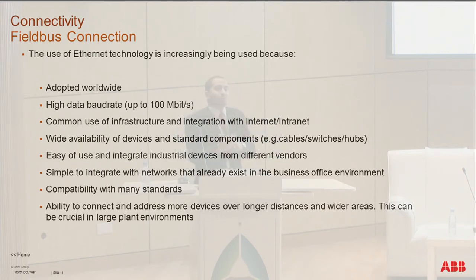It has a higher data baud rate, up to 100 megabits per second. Simple to use. Common use. As you know, each communication protocol needs a specific type of cable, while in Ethernet technology, as we will see with Ethernet IP, Profinet, and IEC 61850, we can use the same type of cable, without any specific type of cable for each protocol. Simple to integrate into any type of network, compatibility with many protocols, and its ability to connect more devices over very long distances, which is very important to apply this type of protocol in a large plant environment. These are the main advantages of using Ethernet technology.